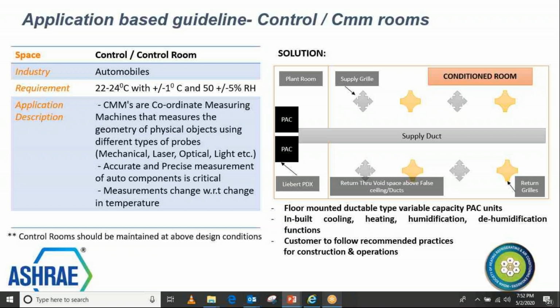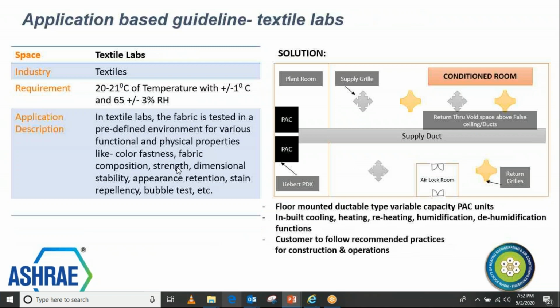In the textile lab, a different application of precision AC, there is quite close control on the temperature. Some people even ask for up to 0.5, but most accept ±1 degree, 20 ±1, and 65 ±2 or ±3, because they go for certification also here. So due to all these reasons, when these labs have to go for certifications, they need to maintain these conditions so that they are able to measure the strength of the fabrics, the color fastness, dimensional stability, appearance, and many other things. So they must have this kind of close control in the room. Distribution of air is also very important in this kind of application, because you cannot pump more air at a certain place and less air at another place.